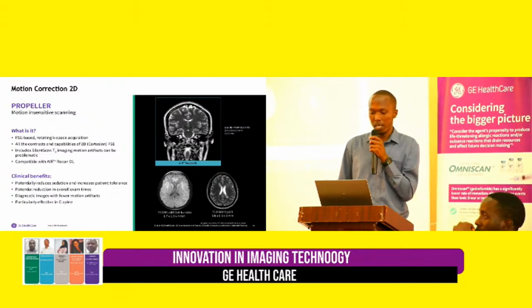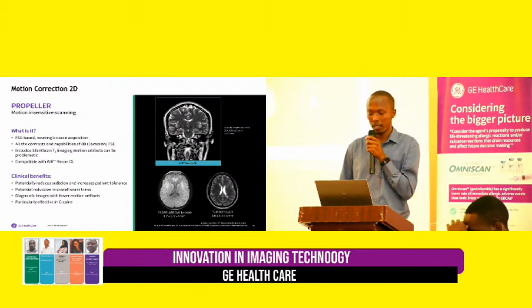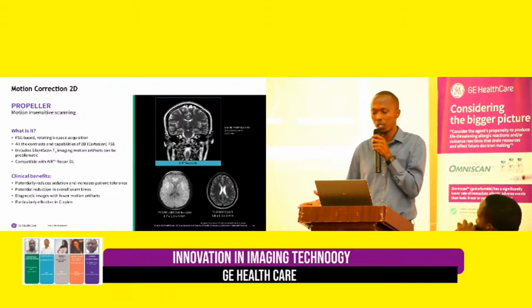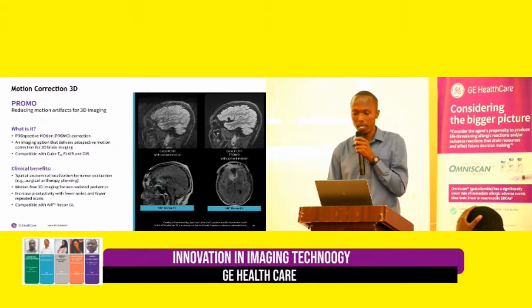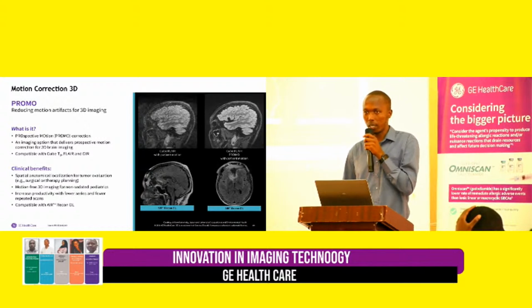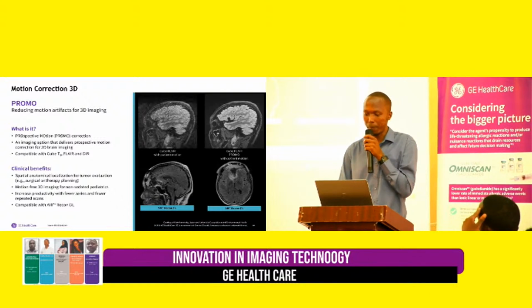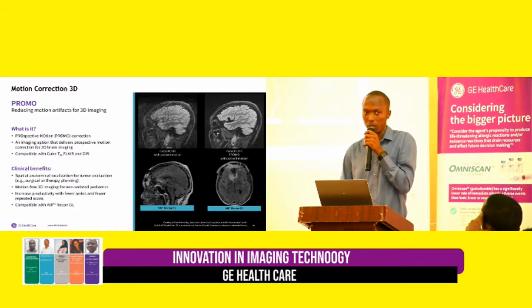With these, we are able to scan patients without sedation, reduce scan times, and reduce artifacts. For 3-dimensional imaging, we use PROMO, which is known as prospective motion correction. This is for 3D imaging techniques, and it's also compatible with AIR Recon DL. It helps us scan patients, including children, without sedating. From this image, you can see the patient is moving and there are a lot of motion artifacts. But with PROMO, for the same patient, we repeat the scan, and it compensates for the motion.